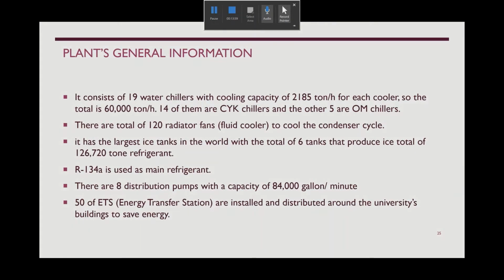The next topic is general information about the plant. The plant consists of 19 York water chillers with a cooling capacity of 2,185 tons for each chiller. So the total is 60,000 tons. 14 of them are CYK chillers and the other 5 are OM chillers. There are a total of 120 radiator fans or fluid coolers to cool the condenser cycle. It has the largest ice tank in the world, with a total of 6 tanks that produce ice of a total of 126,720 ton-hours. R134A is used as the main refrigerant. There are 8 distribution pumps with a capacity of 84,000 gallons per minute. 50 energy transfer stations are installed and distributed around the university buildings to save energy.